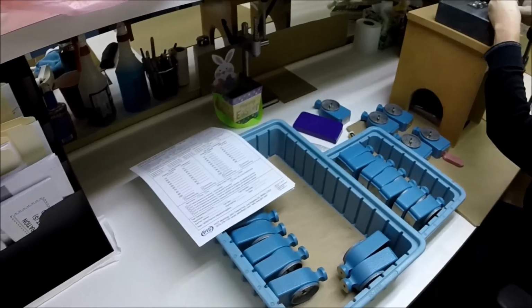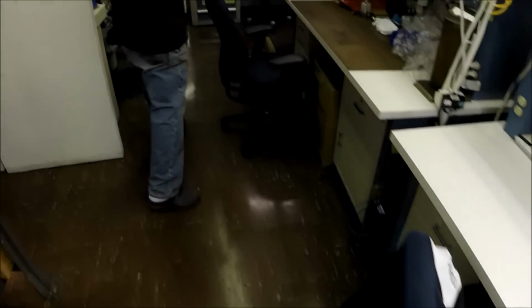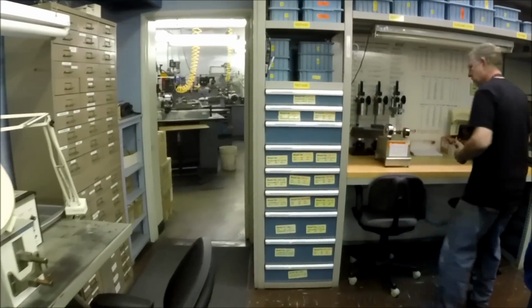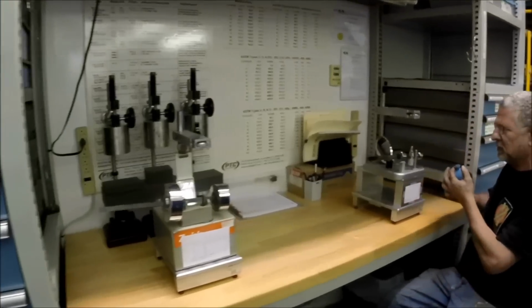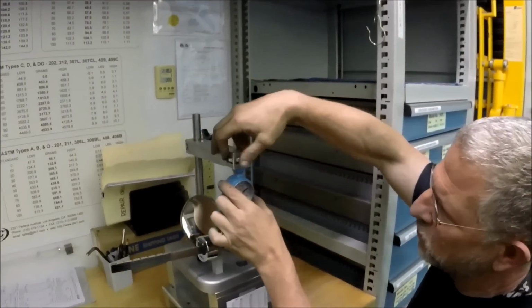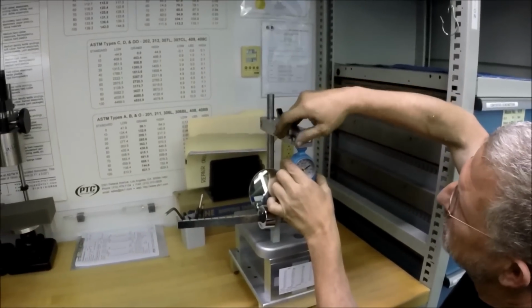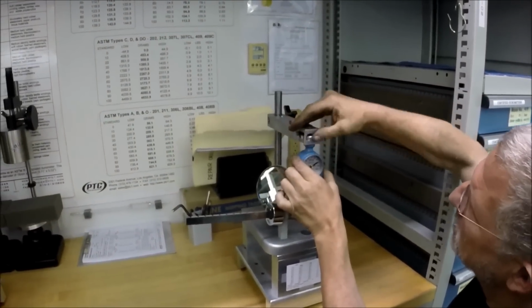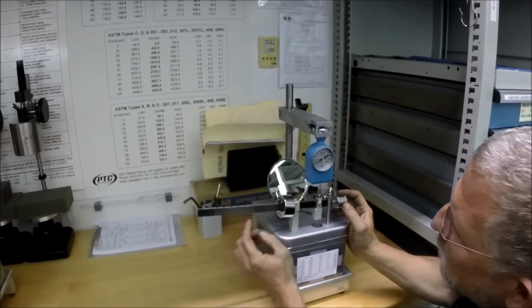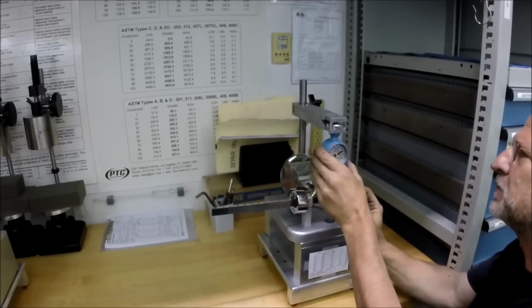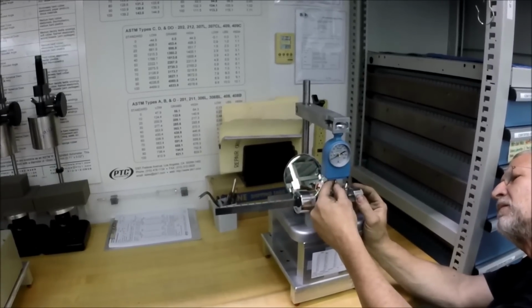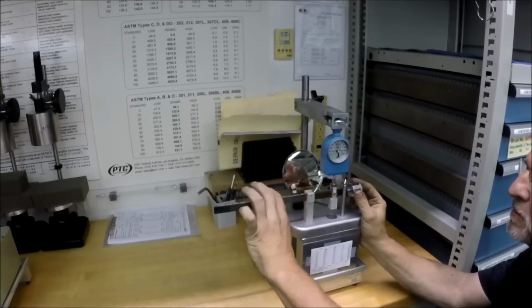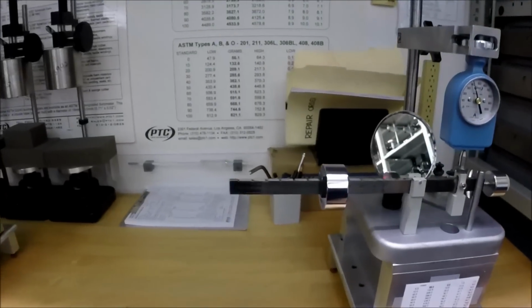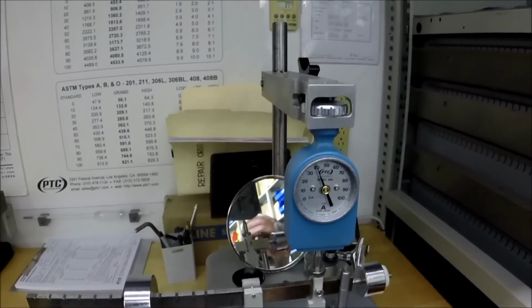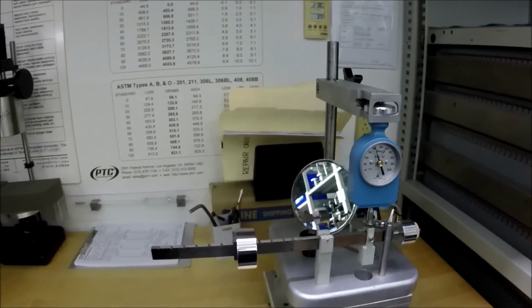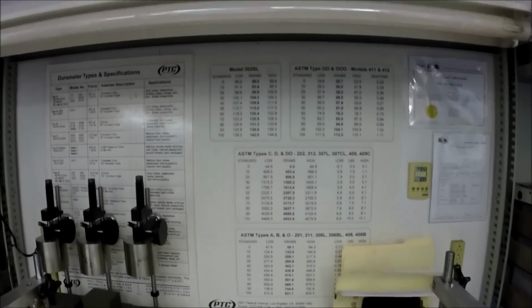Around this side is the station where we can check that the correct force is applied. These are dedicated devices for calibrating the durometer. The durometer mounts on the stand. The weight is moved over, and the reading is then taken off the dial, and it should match when calibrated to the weight. And so that is done at every 10 points. You can see on the wall the actual numbers that are being applied by the ASTM specification.